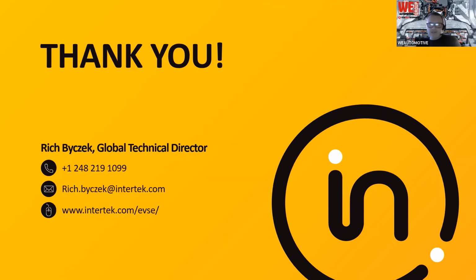Thank you, Rich. Next question: what about EN standards? So in the case of EV charging systems, the EN standards are essentially adopted IEC standards. IEC 61851-1 is adopted in Europe as EN 61851-1. Even within the European Union, each country adopts the EN standard as a national standard, and that becomes essentially the regulatory requirement. So the Swedish version, the German version—don't get me started—the DIN version of that standard is the official regulatory requirement in that country. But in general, these are fully harmonized with the IEC requirements, so a CB scheme certificate to the IEC requirements is generally going to cover all of your CE marking requirements.